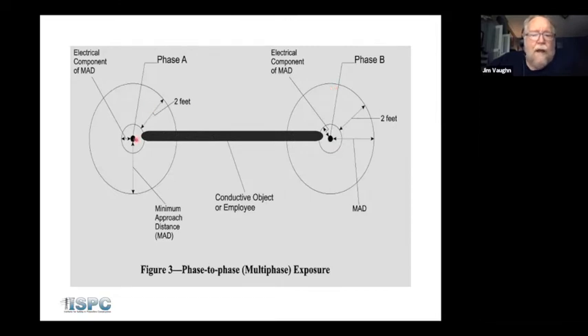Same on B phase. So let's say this is A phase on the right, B phase on the left. If we have a conductive object in our work, so I'm over here and I've got a conductive object, and if that conductive object is long enough to get into the MAD of both conductors, then your exposure is phase to phase. And when you use the tables, you must use the phase-to-phase calculation.